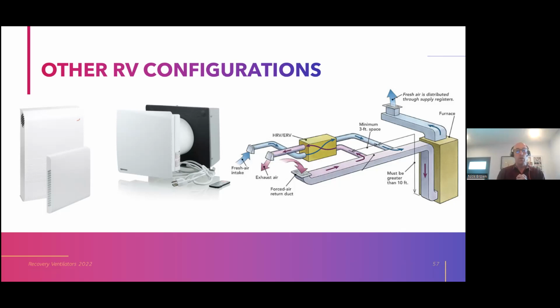And then you can also install your HRV, not with dedicated distribution systems, but shared distribution systems with your HVAC system. So you can duct the stale air exhaust out of the return air and duct the fresh air supply into the supply air.